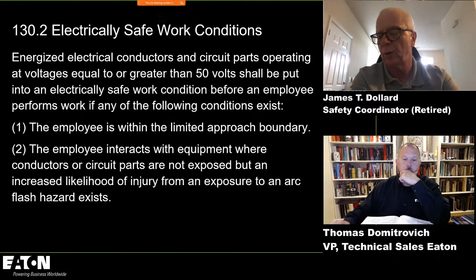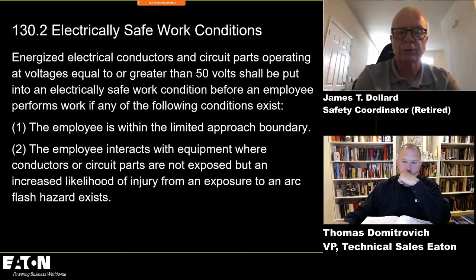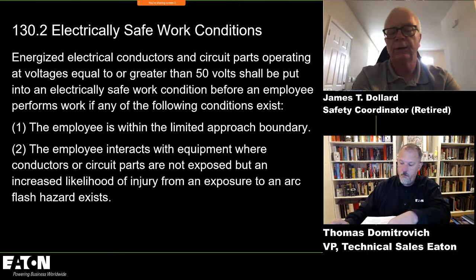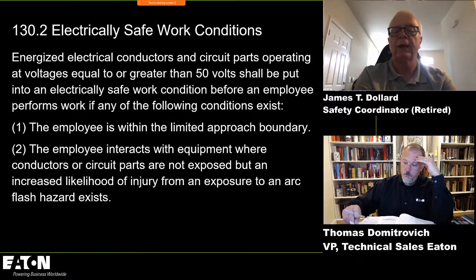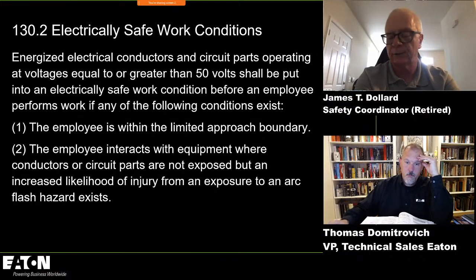So if we've got energized parts, and we're going to get closer than 3'6", then the general rule requires an electrically safe work condition. The second threshold to establish is where an employee is interacting with equipment where conductors or circuit parts are not exposed, but an increased likelihood of injury from an exposure to an arc flash hazard exists. And the best example of that would be, I'm going to be opening and then racking out a 4,000 amp low voltage power circuit breaker. So I'm interacting with the equipment in a manner that increases the likelihood of an arc flash.